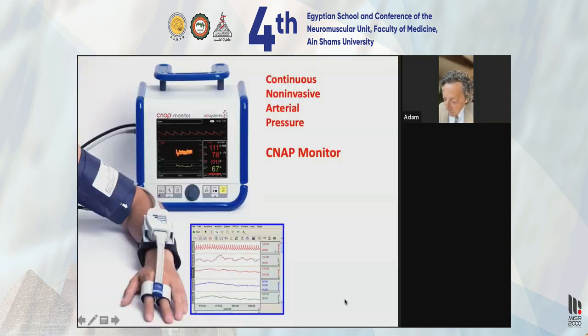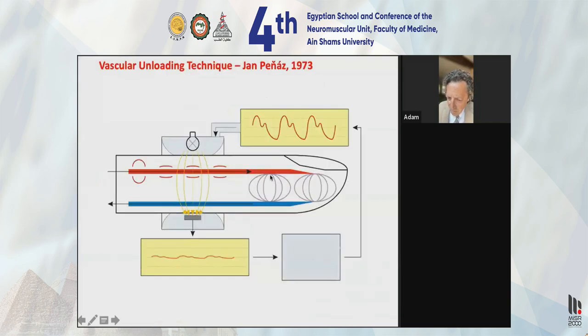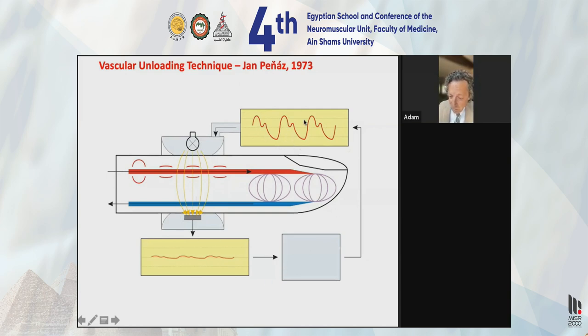The CNAP monitor provides beat-to-beat blood pressure tracing through tandem blood pressure cuffs with pulse oximetry, equivalent to an arterial line. It is not a great absolute measurement but is more useful for measuring relative fluctuations of blood pressure. It is a proprietary technology based on work by Jan Peňáz in 1973, showing that volumetric analysis of the finger could produce a servo loop approximating blood pressure changes.